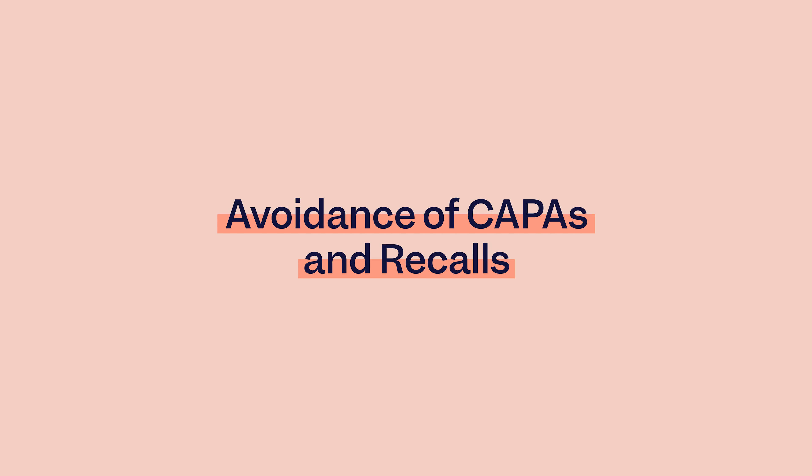Risk management is a process that can help you gain knowledge to identify the risks of a medical device. This knowledge can be used to detect design flaws that have a safety impact in the development phase. The sooner the design flaw is corrected in the design phase, the less expensive it is to fix it. Product recalls are necessary when a medical device with safety violations is sold in a market. Recalls are detrimental to the manufacturer's reputation and often carry excessive costs, legal fees, lawsuits and fines.